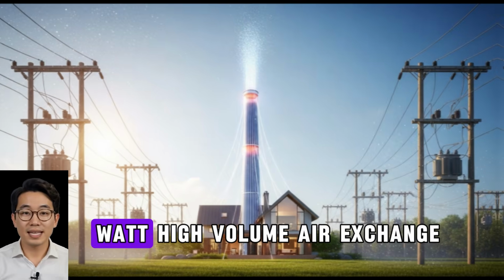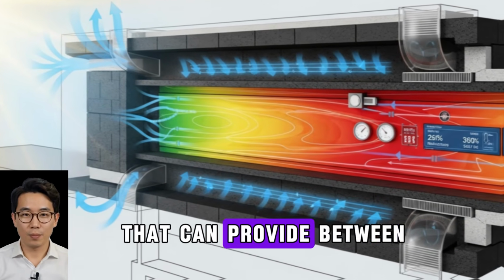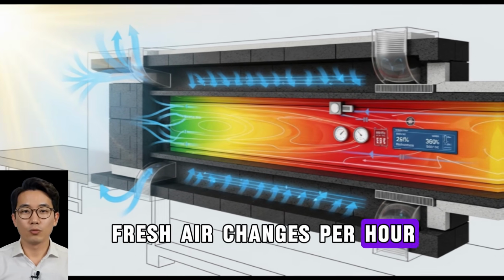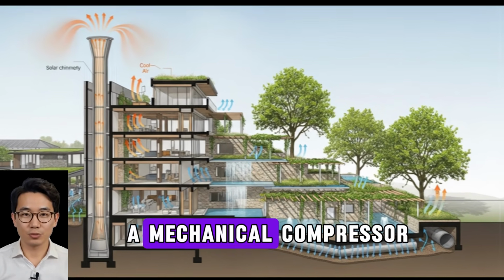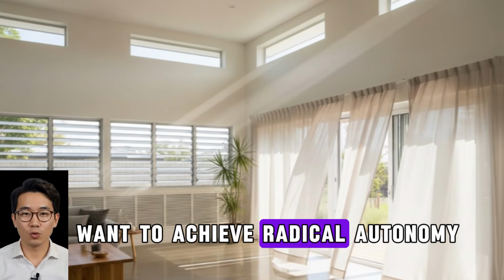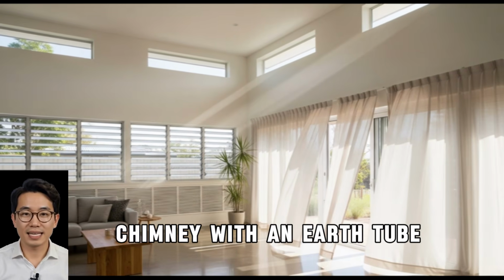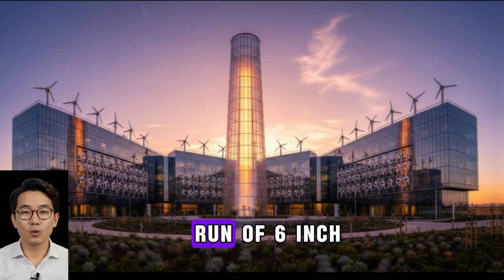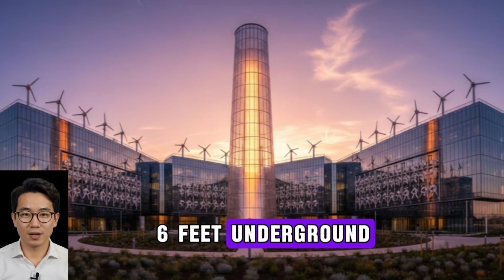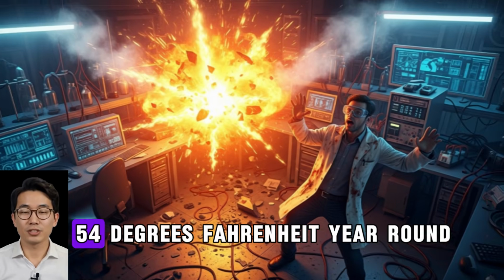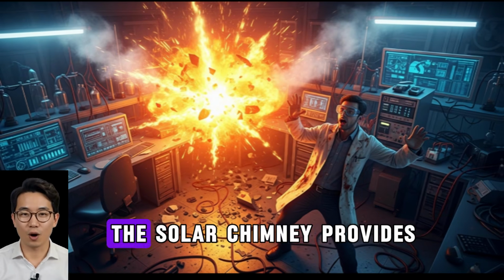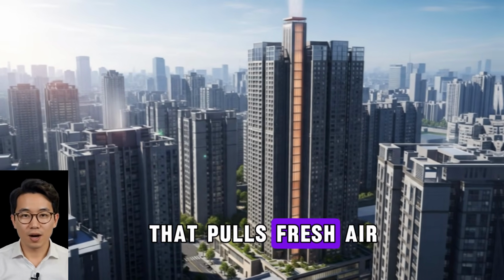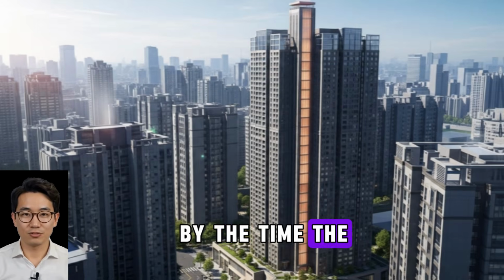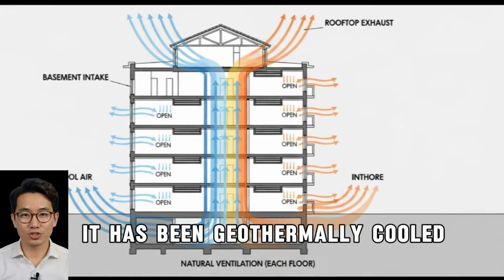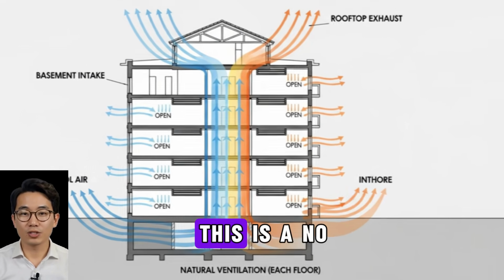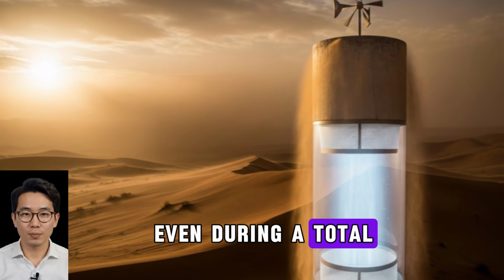This creates a 0-watt, high-volume air exchange that can provide between 8 and 12 fresh air changes per hour, effectively replacing the need for a mechanical compressor. And if you really want to achieve radical autonomy, you pair your solar chimney with an earth tube. You bury a 100-foot run of 6-inch PVC or clay pipe 6 feet underground, where the temperature remains a constant 54 degrees Fahrenheit year-round. The solar chimney provides the suction that pulls fresh air through that pipe. By the time the air reaches your living room, it has been geothermally cooled to 70 degrees Fahrenheit. This is a no-watt air conditioner that works even during a total grid collapse.